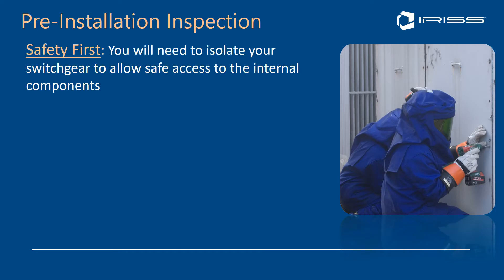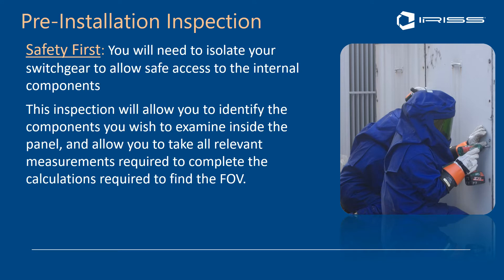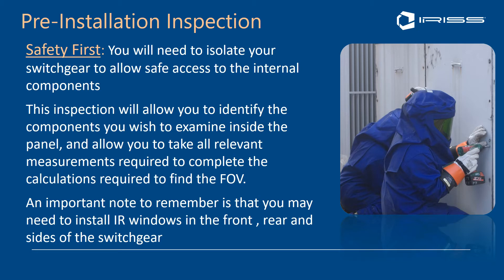Safety is obviously paramount. You should isolate your switchgear to allow safe access to internal components before doing this inspection. The inspection will allow you to identify the components you wish to examine inside the panel and to take any relevant measurements required to complete the field of view calculations, which we covered in webinar five of this series. You may need to install IR windows in the front, rear, or sides of the switchgear to ensure complete measurements.